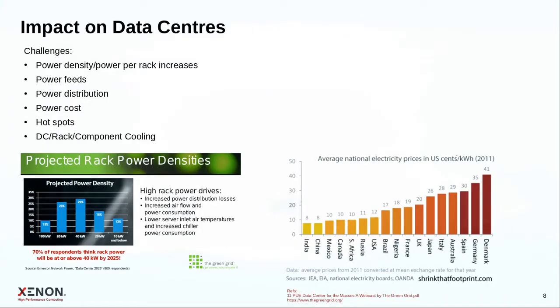That's one part of the equation on the component side. At a higher level in the data center, we have similar problems where all of this comes together, where power density per rack increases. This is a projection for 2025 for power consumption per rack. We're typically in commercial data centers now somewhere in the order of 6 to high density racks, or 10 kilowatts per rack. The expectation is we're going up to 20, with a median of maybe 40 kilowatts per rack, and there are designs to go up to 80 and 100 kilowatts per rack unit. The question is how are we going to handle that?